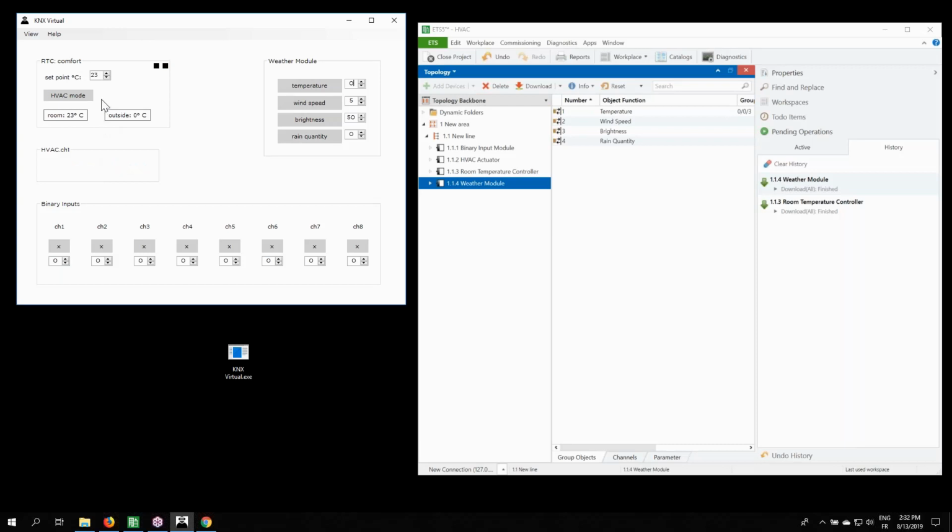Also here there is a standby mode. That means that when I'm not in the room, then 18 degrees is already fine. So by nature, the room temperature will drop until 18 and even 17. And that is then the trigger for the RTC to open the heating valve again until it reaches 18 again, and so on and so on.